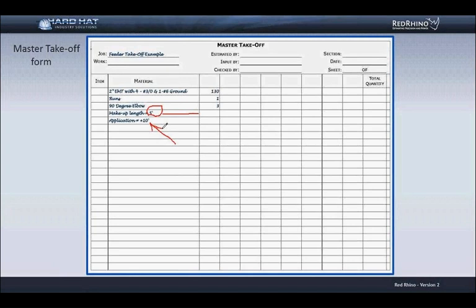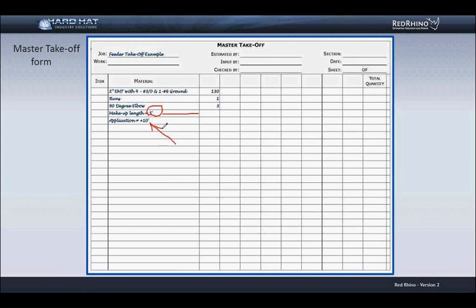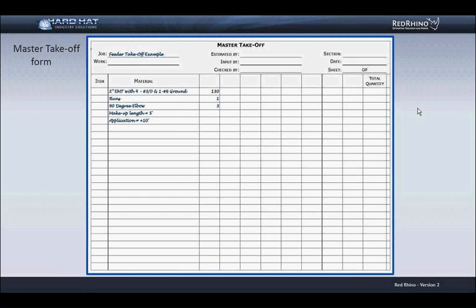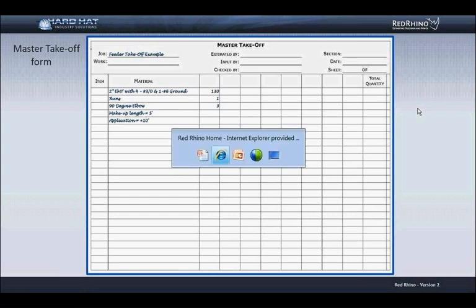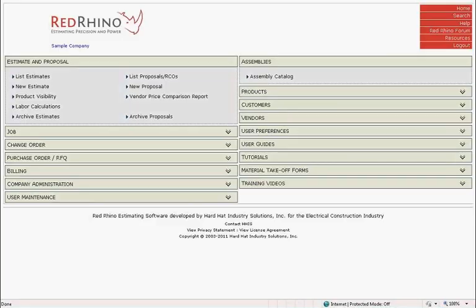The next definition you need to know is conduit application. Conduit application refers to the manner in which the conduit must be installed. Red Rhino adds labor based on level of difficulty to install the conduit. Red Rhino considers six different applications. Normal application is six feet off the floor. Concealed, the conduit would be installed inside walls. Exposed plus 10 feet, the conduit would be installed above 10 feet off the floor. Exposed plus 20 means conduit would be installed 20 feet off the floor. Slab application, conduit would be installed around concrete forms. In underground application, conduit would be installed in a trench. In this example, the conduit would be installed above 10 feet off the floor. Now this concludes the portion of the material takeoff.